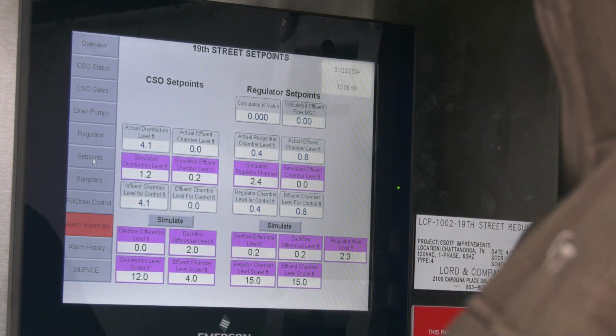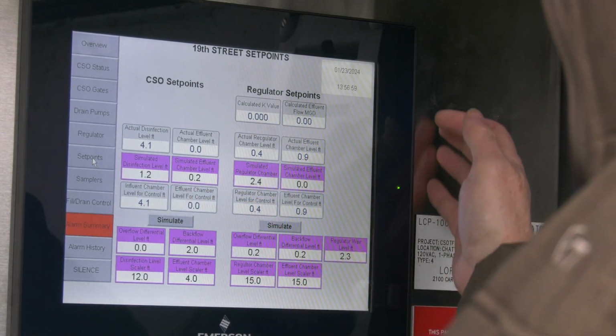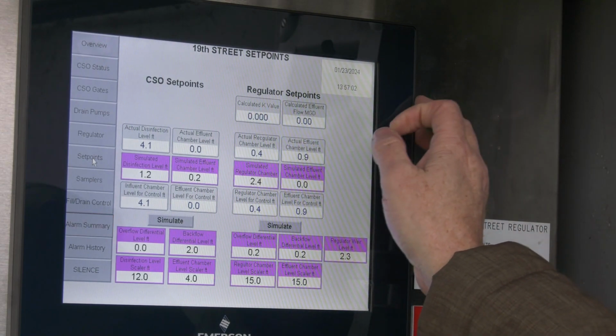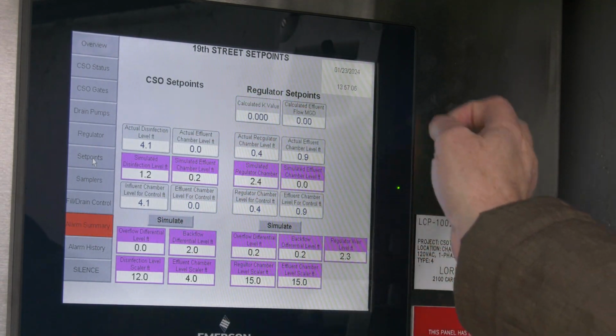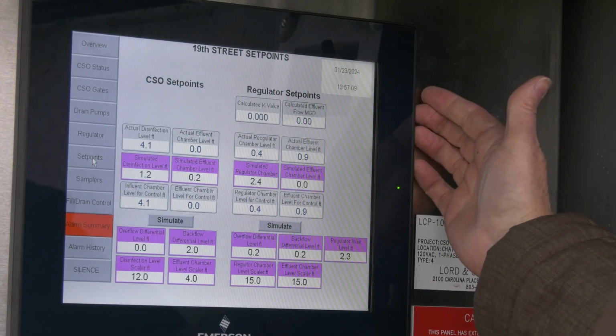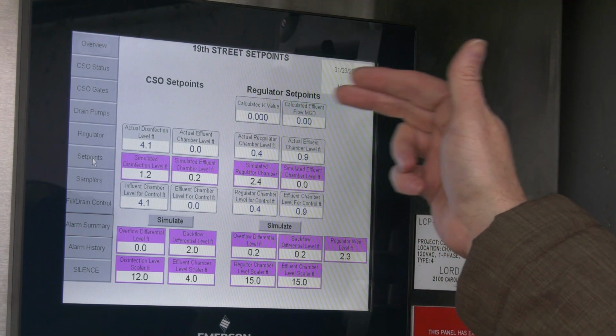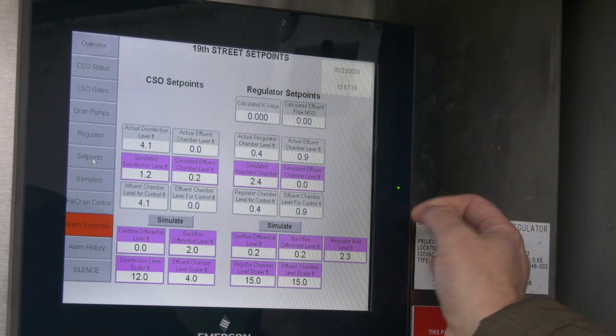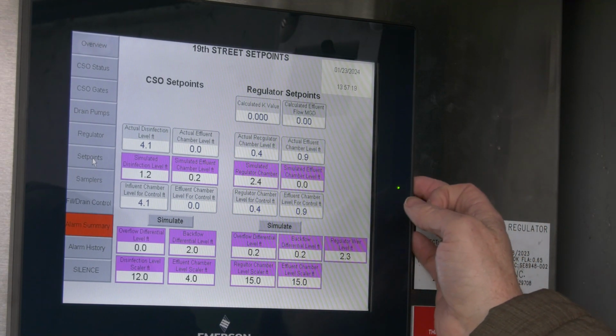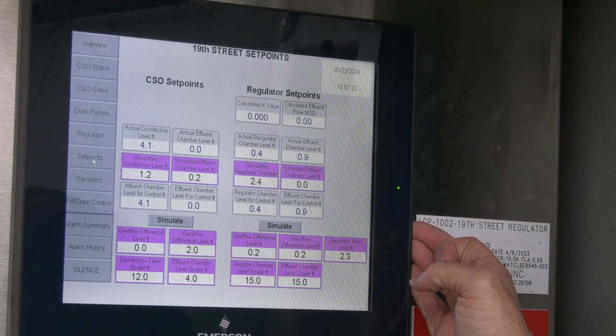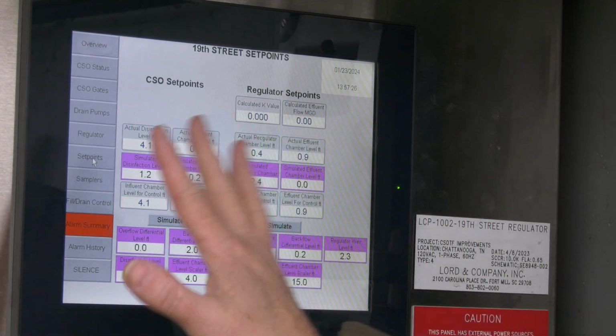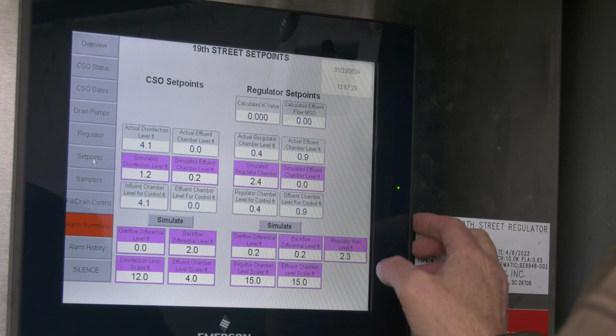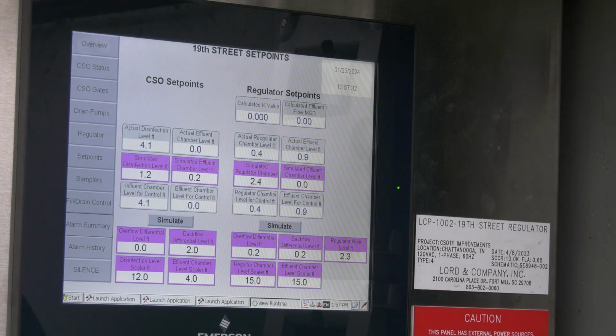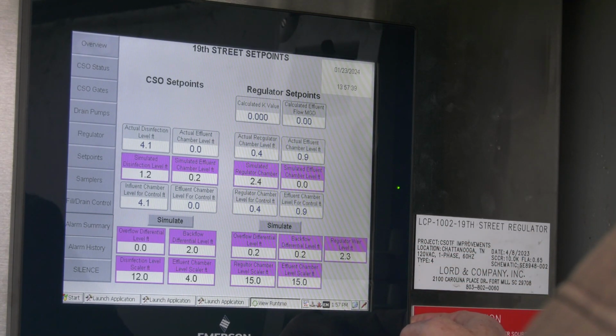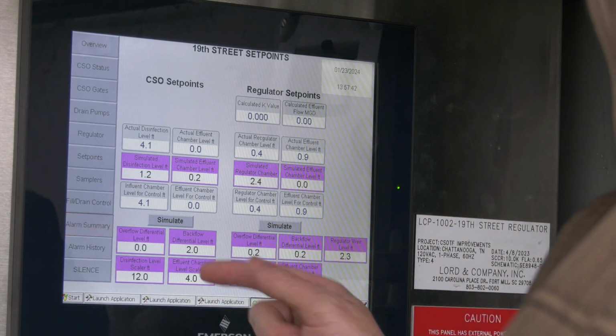Okay. All right. See, set points. This is set points for the actual CSO for filling. The regulator set points: K value. You guys don't need to set the K value. That's just used to calculate the flow over the weir. Let's see here. The actual regulator chamber level, effluent chamber level, regulator chamber level for control, effluent chamber level for control in feet. These are feedbacks, and you've got simulated, which you don't need to ever use. Overflow differential comes from the difference between these two ultrasonics. Let's see here. That's pretty much it for this.